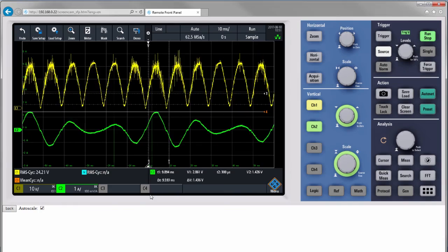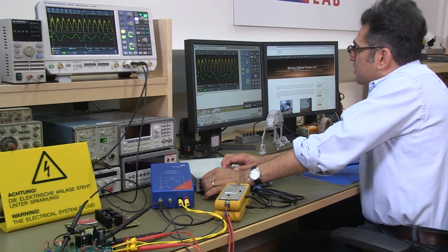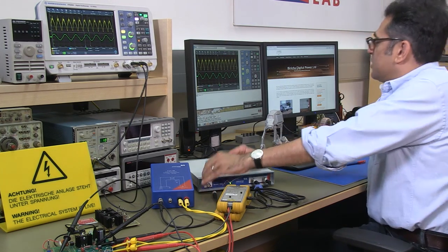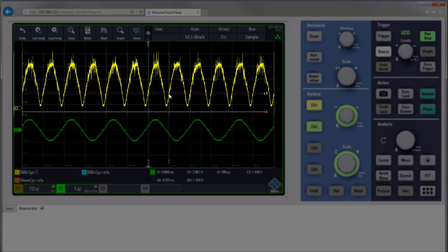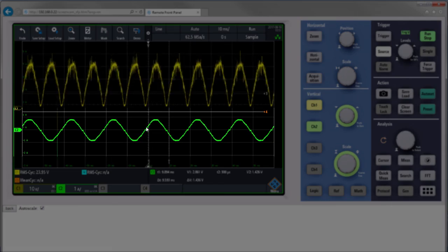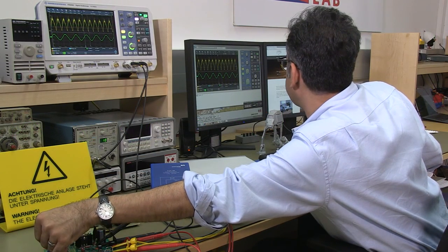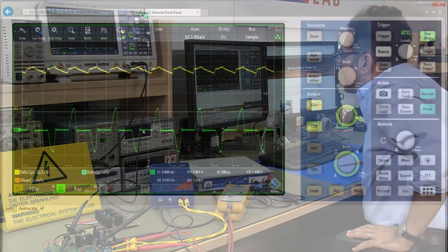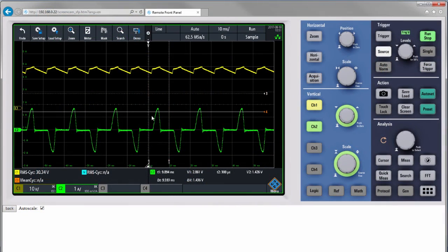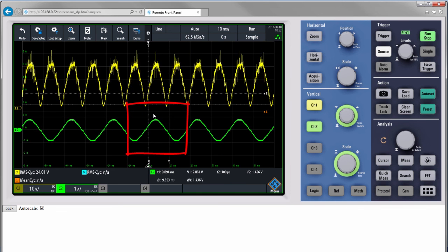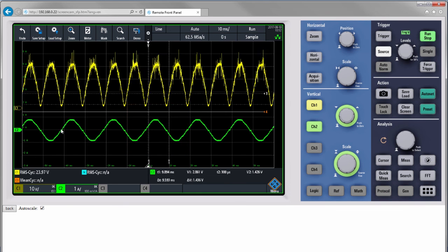Finally let's have a look at the transient, let's have a look at some of the waveforms on the oscilloscope. So if I go to my scope I need to disconnect Bode so that the injection signal does not corrupt. There we go. Now the yellow trace is the reference rectified voltage waveform and the green trace is the current that I'm measuring. So first I'm going to turn off the PFC and you'll see immediately that you get the classic sharp rise of the current and this is what the regulation is all about. Nobody likes these sharp peaks and that's why we have to use PFC.